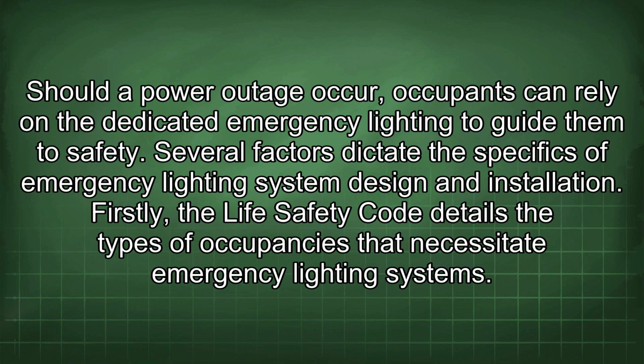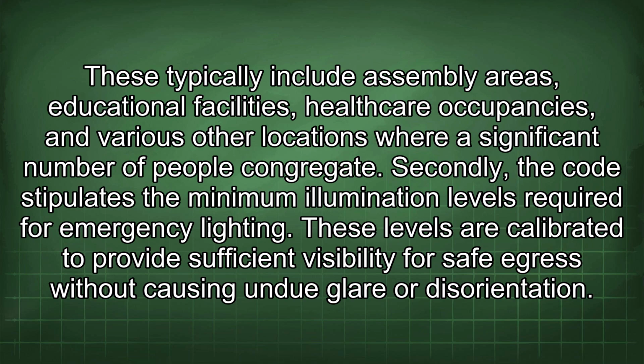Should a power outage occur, occupants can rely on a dedicated emergency lighting to guide them to safety. Several factors dictate the specifics of emergency lighting system design and installation. Firstly, the Life Safety Code details the types of occupancies that necessitate emergency lighting systems. These typically include assembly areas, educational facilities, healthcare occupancies, and various other locations where a significant number of people congregate.